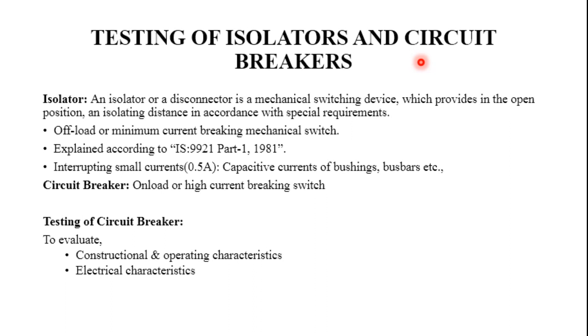Isolators interrupt only a very small amount of current, of the order of 0.5 amperes, which may be capacitive current from bushings, bus bars, etc. There is a definition for the isolator or disconnector as per Indian standard IS 9921 Part 1, 1981.